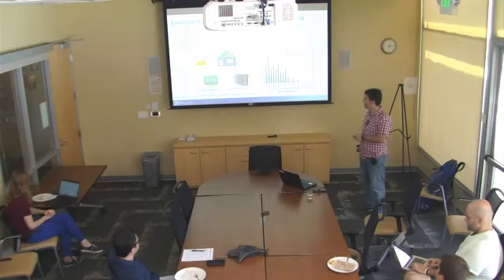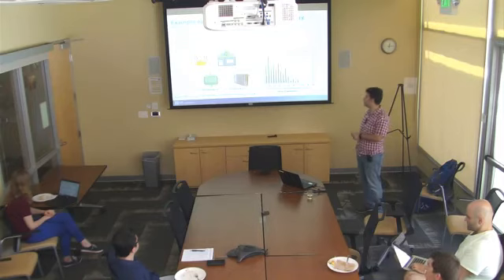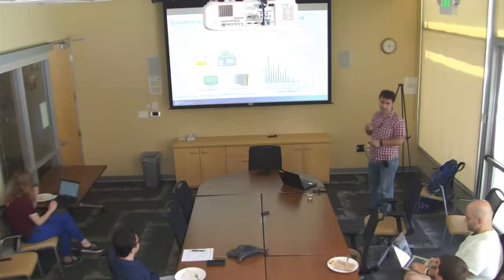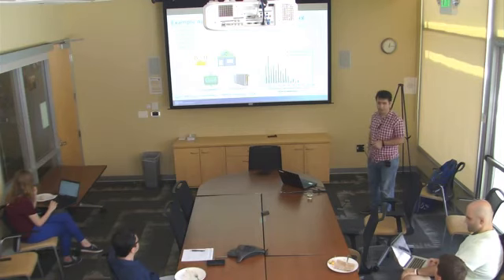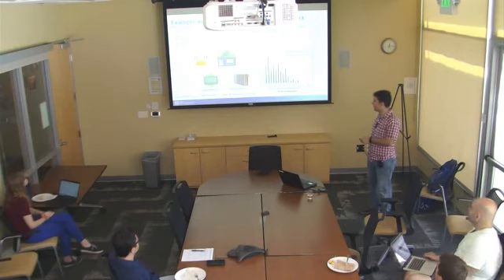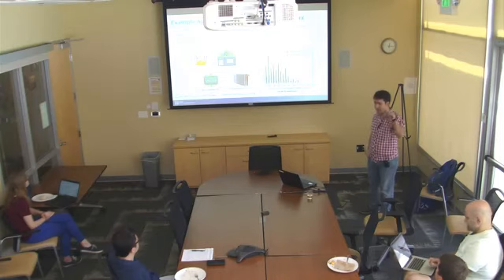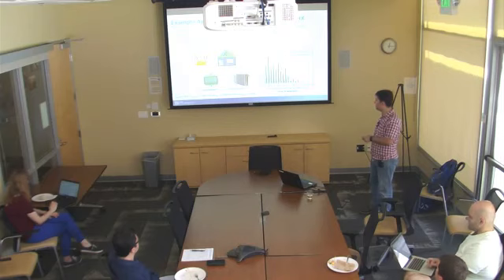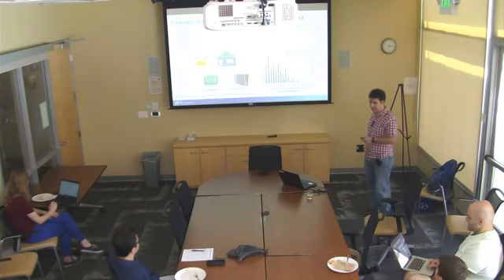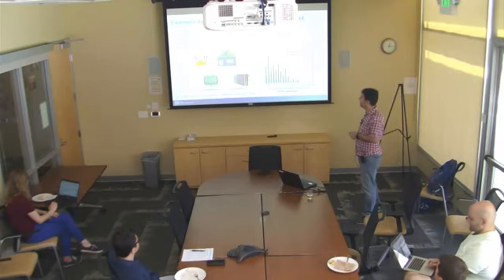So if they were using fin tube heat exchangers in the coupled model here, they ended up with this chart, which shows the number of hours for the load that the residents needed, but this approach was not sufficient to provide that amount of cooling. Of these 539 hours, this system coupled with the fin tube was not successful in providing cooling for 140 hours. But we said, okay, instead of this, let's go with the microchannel heat exchanger and see how many unmet hours there would be. This showed that we can reduce that to less than a third, 45 hours, if we use this plastic heat exchanger under the same conditions, the same flow rates, which were about 1200 CFM and 5 gallons per minute of chilled water coming into the air handler.